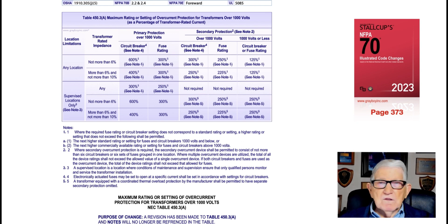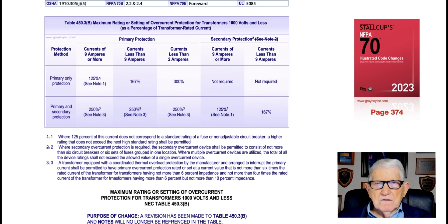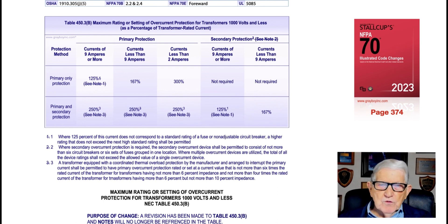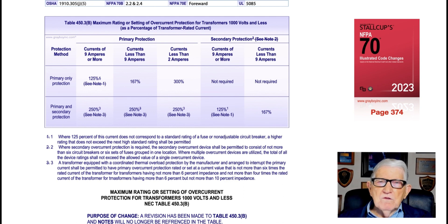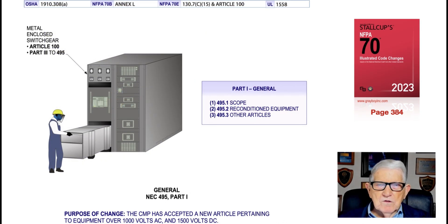Be very aware that there are changes in this table as well as the notes. This illustration deals with the maximum rating or setting of an overcurrent protection device for transformers 1,000 volts and less in accordance with new Table 450.3(B). The purpose of the change here was simply to delete the lettered notes and use numbers to reference the information below the table. That's what this revision is about — warning the user of the NEC what took place in Table 450.3(B).